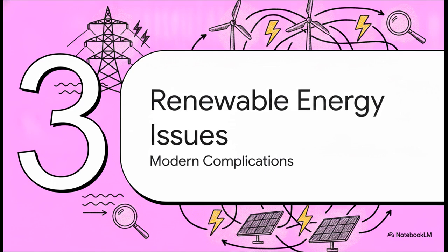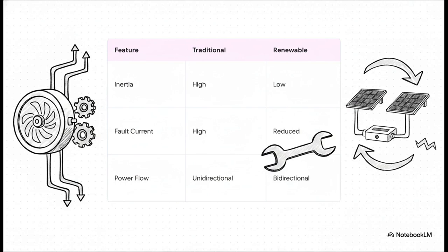Section 3. Renewable energy protection challenges. That traditional setup we just talked about has worked beautifully for decades. But, as you know, the grid is changing rapidly. Integrating solar and wind power completely changes how we detect these faults. Traditional power grids were built around synchronous generators. Think massive spinning turbines with high inertia that naturally resist sudden changes and pump out a really high, easily detectable fault current. But renewables, they're inverter-based resources.